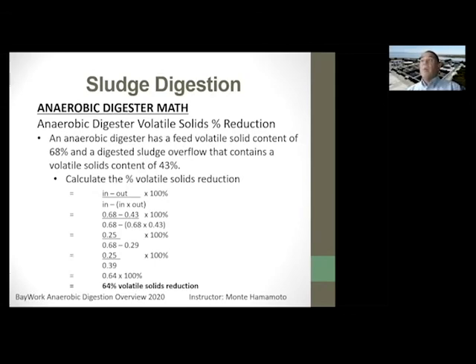So that's 43%. You have 68% solids going in, 43% volatile solids coming out. So how much did we actually reduce the volatile solids going in? The volatile solids calculation is in minus out divided by in minus in times out, turned into a percentage.